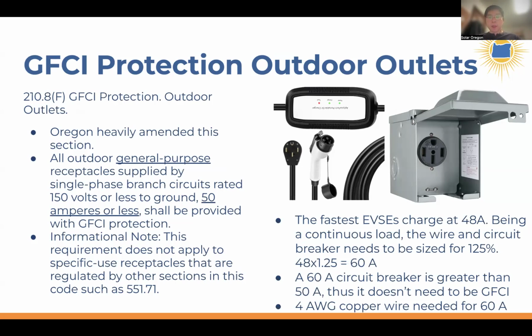So the question is, why would a level one charger require GFCI protection but a level two over 50 amps not require it? Well, technically even a level one wouldn't need a GFCI for the EV charging itself, but it's to protect against using that same outlet for something like a weed whacker or holiday lights, which have less built-in protection. That's why a general purpose receptacle needs GFCI protection.